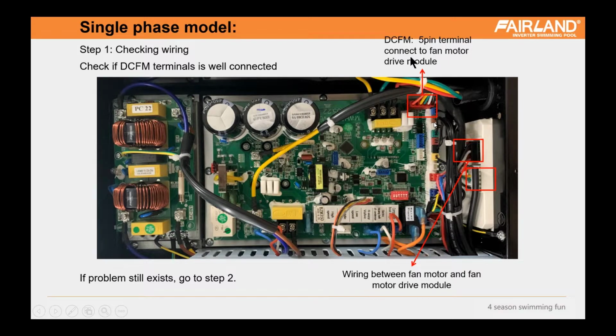Firstly, we have the wiring connected with the drive module. On the integrated board is the DC fan motor 5-pin terminal, and this terminal wire will connect to the fan motor drive module, and the drive module will connect to the fan motor. So we need to check these three parts. Check if the wire connection is well connected or not. You can pull off the wire and replug it again, and use your finger with a little power to pull it to see if it is well connected.